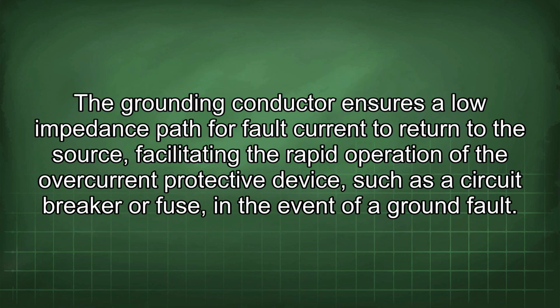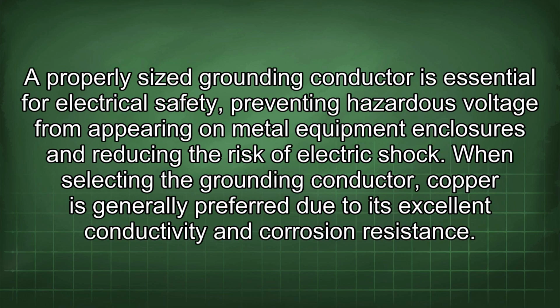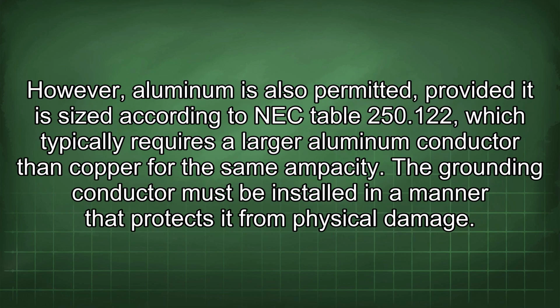The grounding conductor ensures a low impedance path for fault current to return to the source, facilitating the rapid operation of the overcurrent protective device, such as the circuit breaker or fuse, in the event of a ground fault. A properly sized grounding conductor is essential for electrical safety, preventing hazardous voltage from appearing on metal equipment enclosures and reducing the risk of electric shock. When selecting the grounding conductor, copper is generally preferred due to its excellent conductivity and corrosion resistance. However, aluminum is also permitted, provided it is sized according to NEC Table 250.122, which typically requires a larger aluminum conductor than copper for the same ampacity.